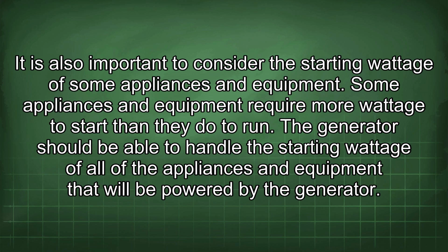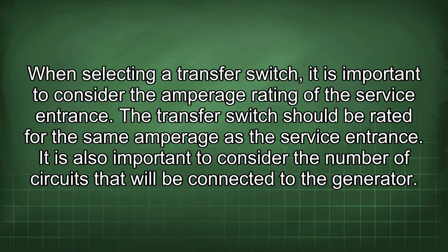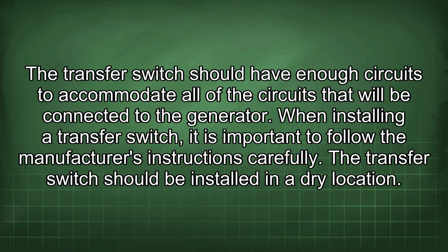The generator should be able to handle the starting wattage of all of the appliances and equipment that will be powered by the generator. When selecting a transfer switch, it is important to consider the amperage rating of the service entrance. The transfer switch should be rated for the same amperage as the service entrance. It is also important to consider the number of circuits that will be connected to the generator. The transfer switch should have enough circuits to accommodate all of the circuits that will be connected to the generator.